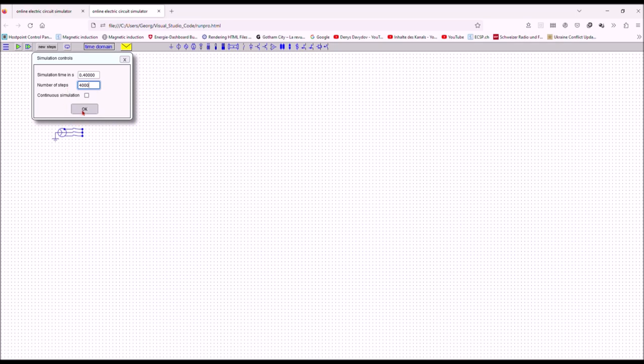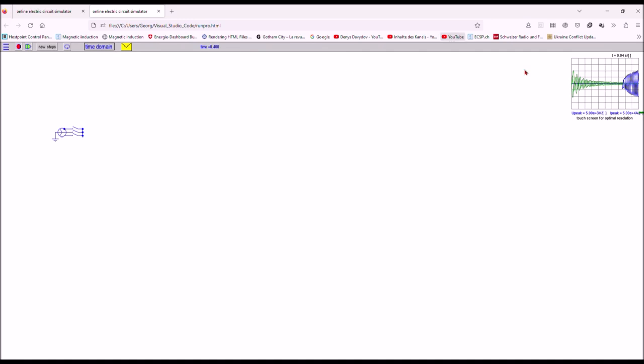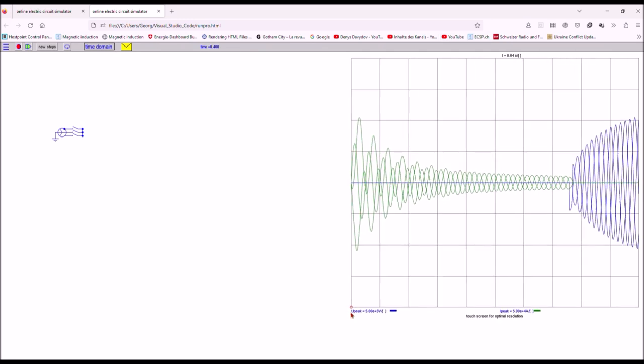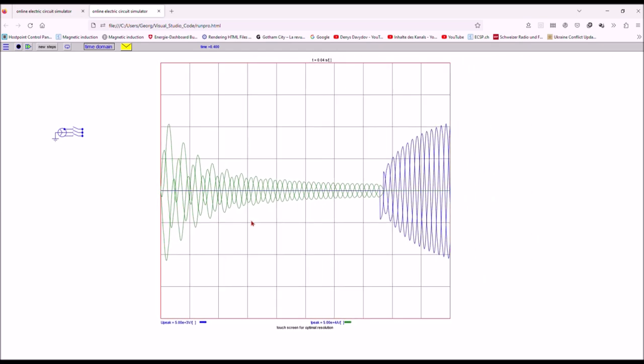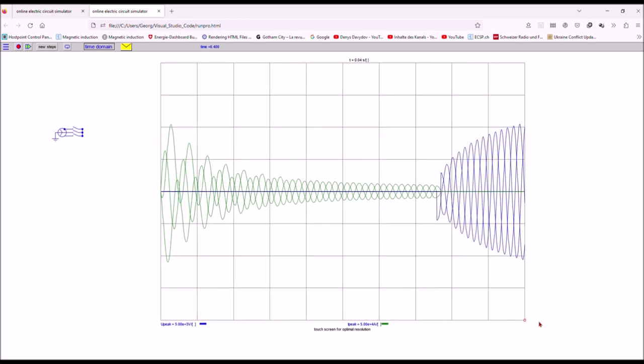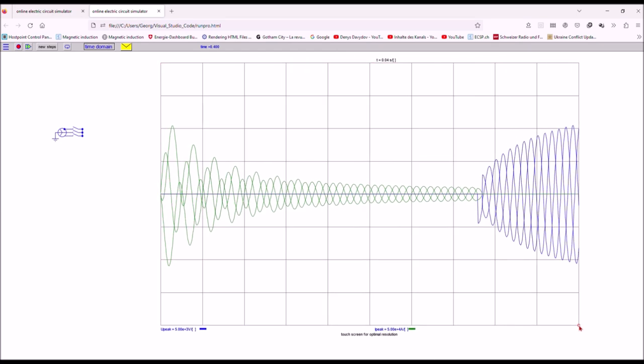I run the simulation and quickly I get the result. Here you see the green is the short circuit current, three phases. And after current interruption of the breaker I see the voltage recovery across the breaker in blue.